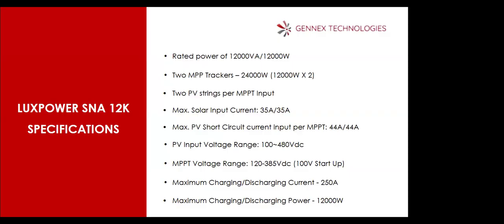PV input voltage range is between 100 volts DC to 480 volts DC. You know why? The 100 volts is just to wake up. That's when the MPPT wakes up and sees that there is a signal from the solar panels. But at that point, you cannot really deliver any power to the box.